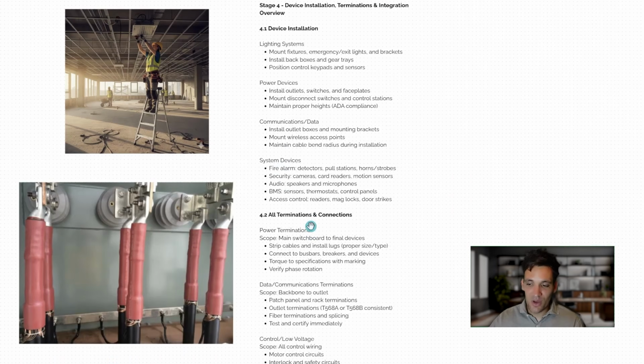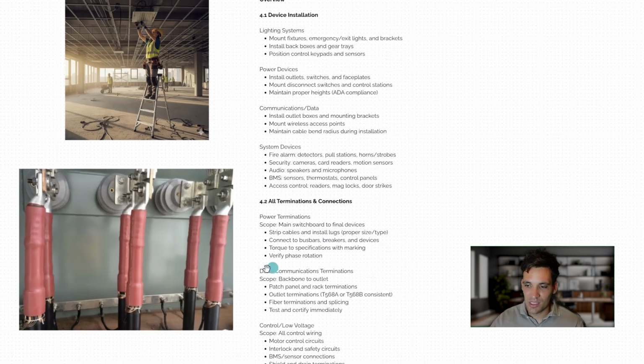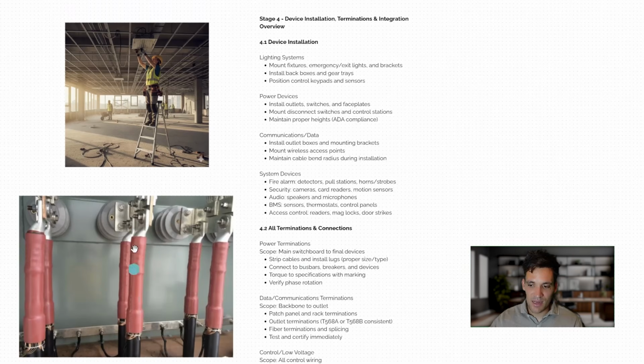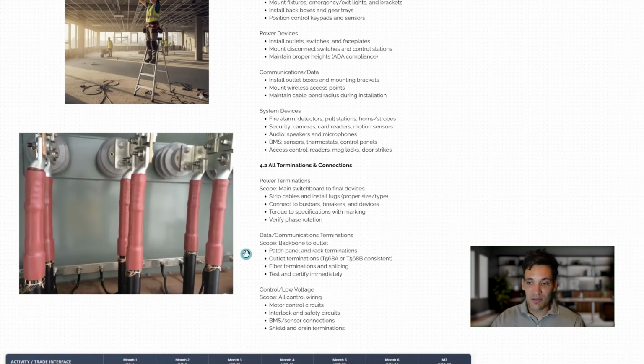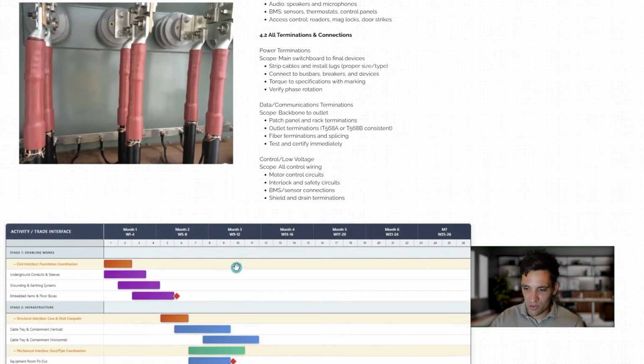And then once the devices are in and we've run all our cables, we need to go and terminate all our cables. Once we've installed the cable, we just have an end of a cable. We need to cut the ends off, install the lugs, crimp the lugs, put on the heat shrink and terminate all the earthing. Then we've got our fully connected electrical system.